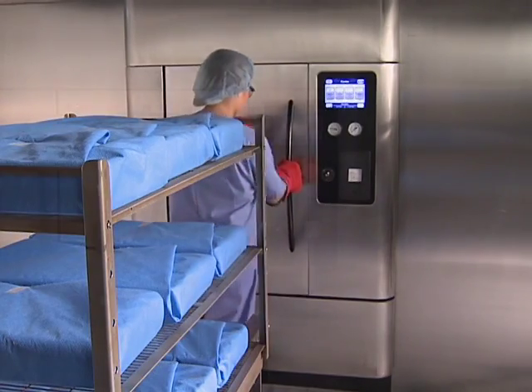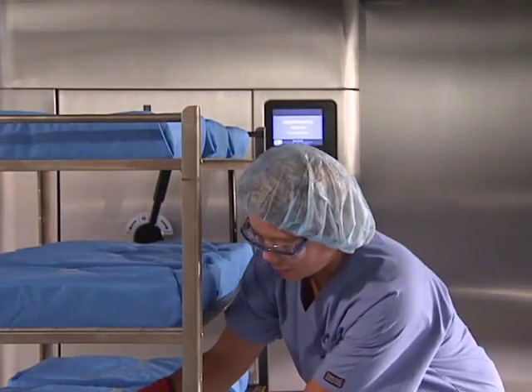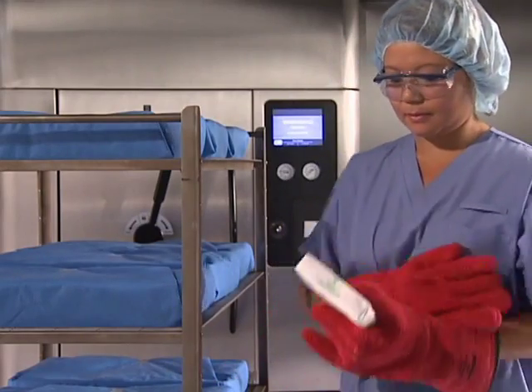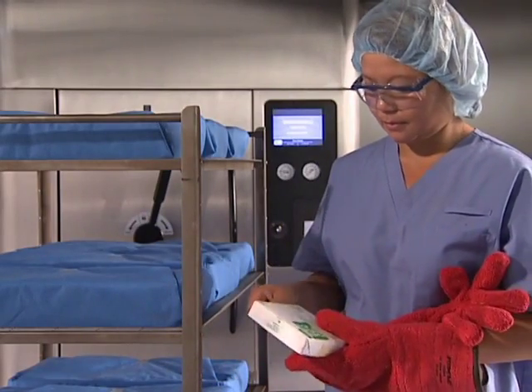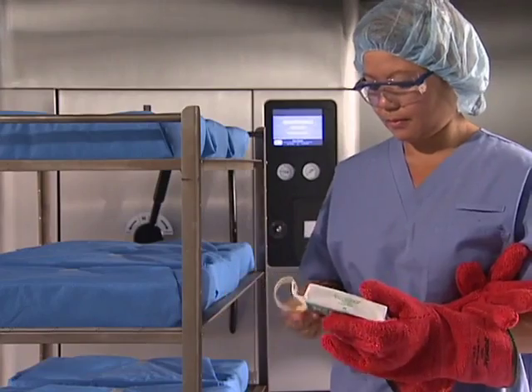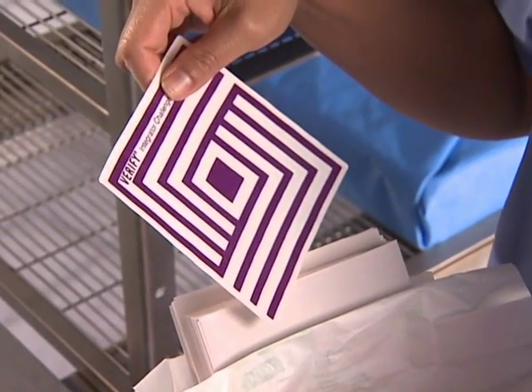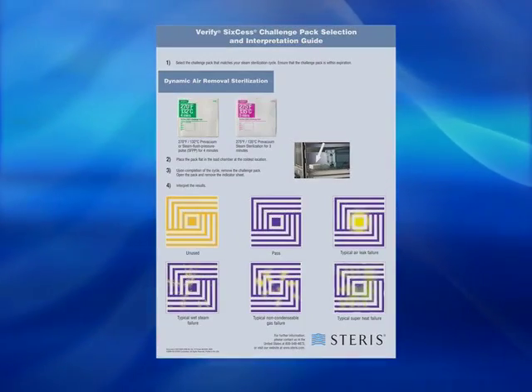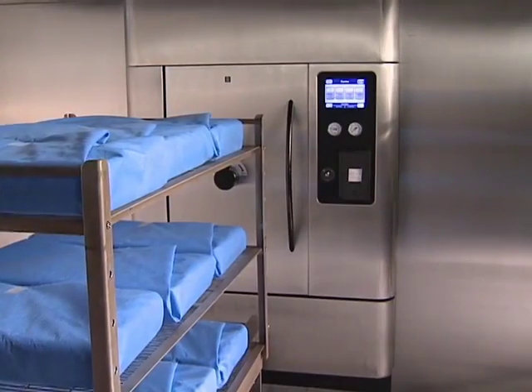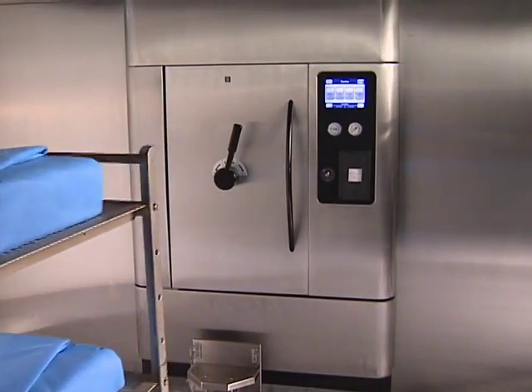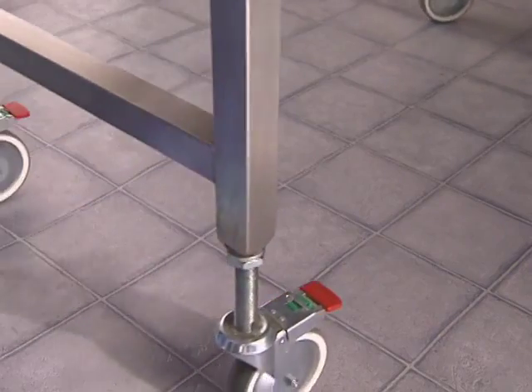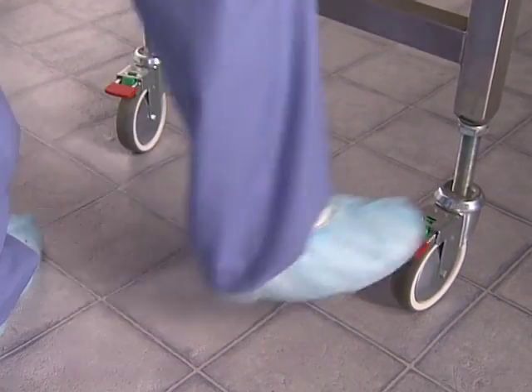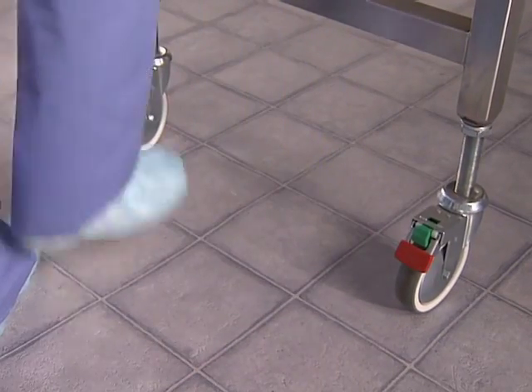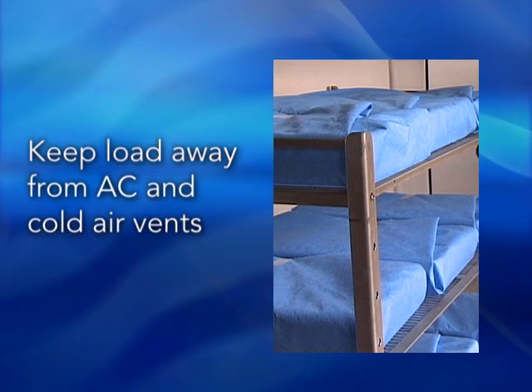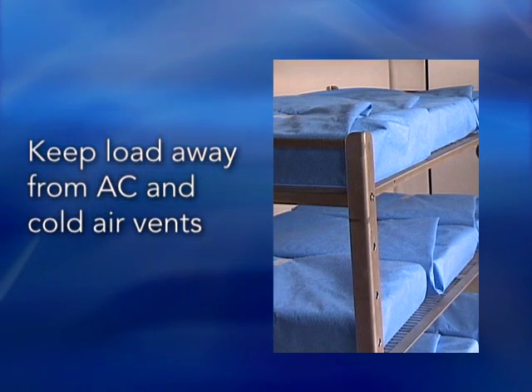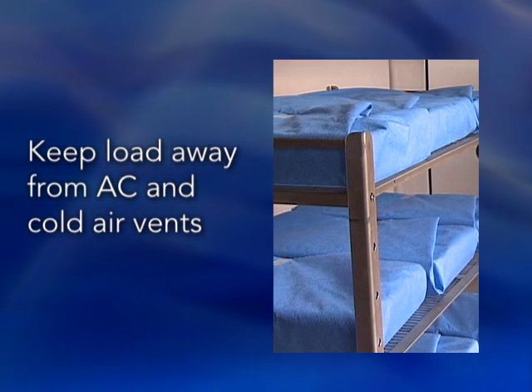Close the chamber door. Upon completion of the cycle, remove the challenge pack. Exercise caution as the challenge pack contents may be hot. Open the pack and remove the indicator sheet. Interpret the results using your Verify SixCess wall chart. Transfer the load from the sterilizer area according to your department's procedures. If desired, the transfer carriage may be parked in place by locking the rear casters. To prevent condensation from forming on the instruments, keep the load away from air conditioning and cold air vents.